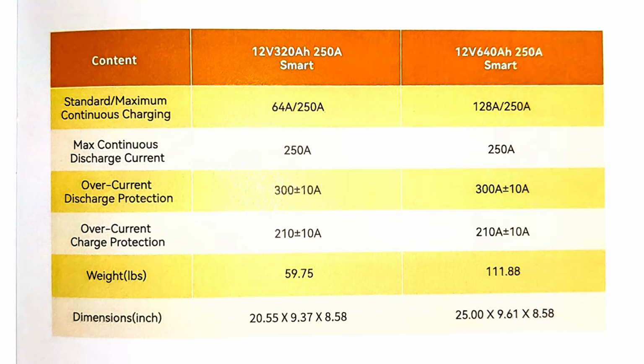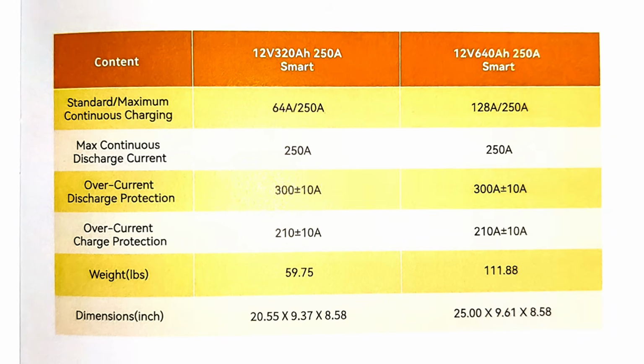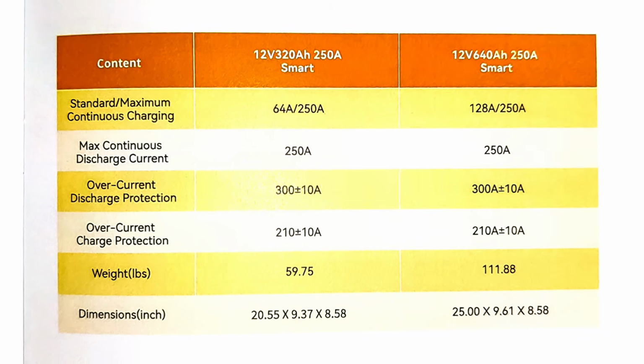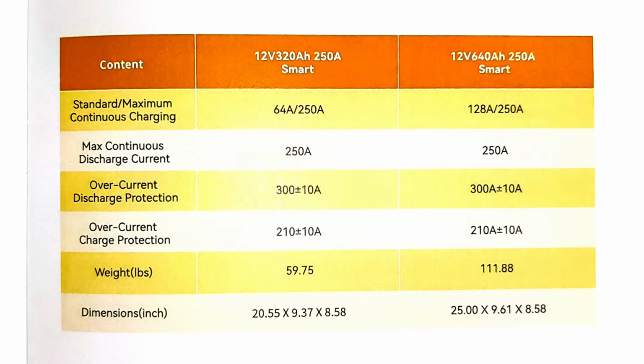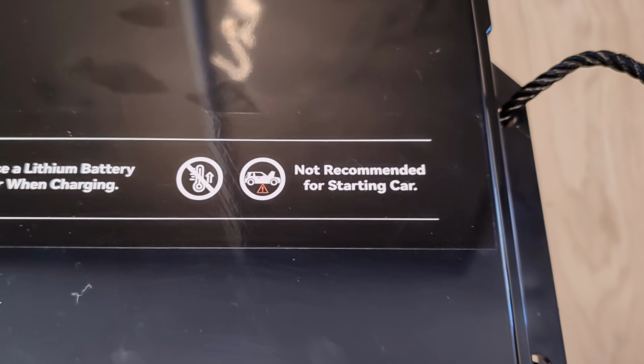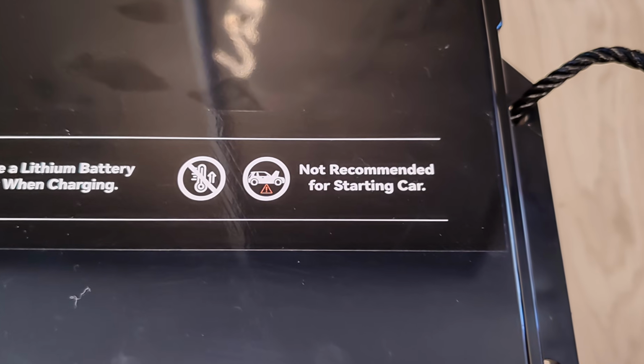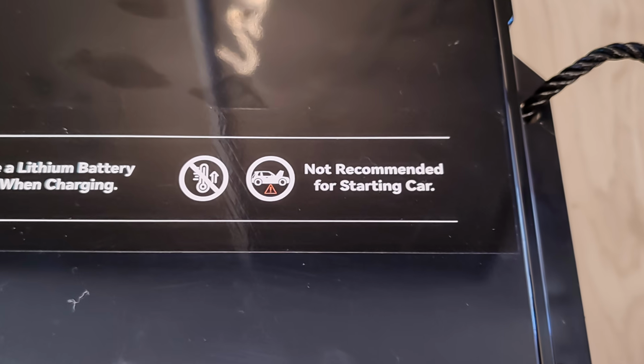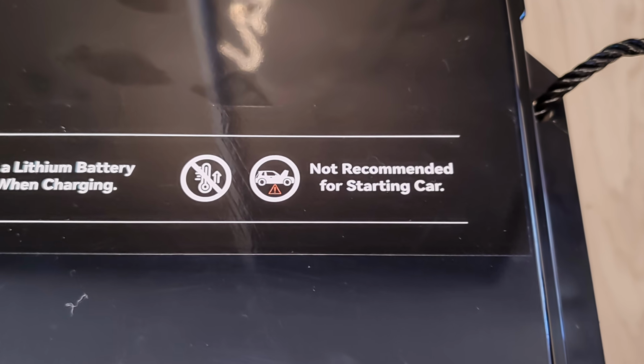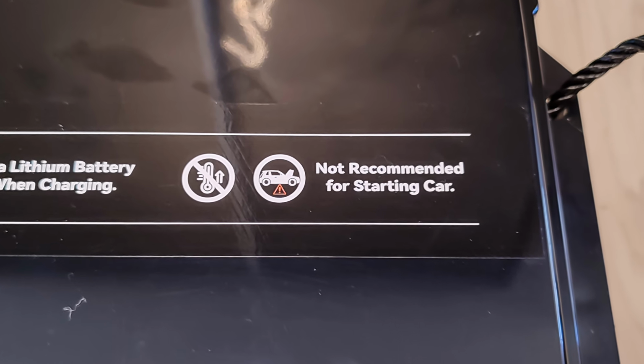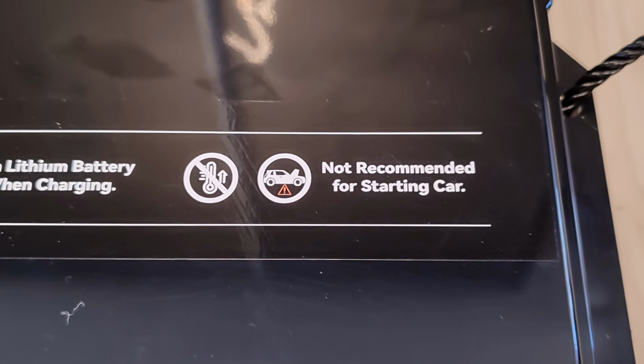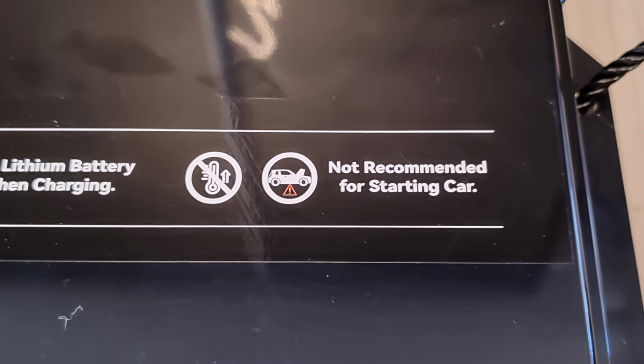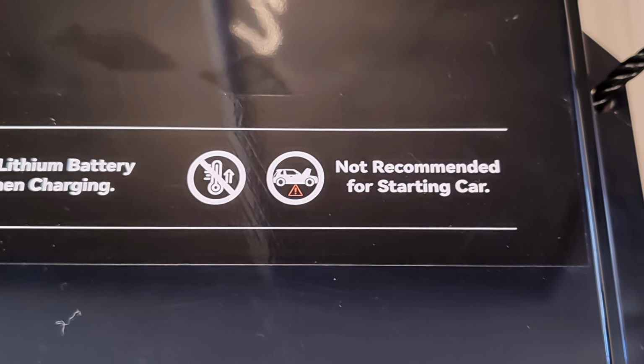The discharge current is 250 amps, with protective shutdown at 300 amps plus or minus 10 amps. There is a warning on the case that the battery must not be used as a starter battery for starting cars, and this is correct, because for gasoline cars the starting current is usually around 300 amps, and for diesel cars it is even higher, so the BMS will simply go into protection.